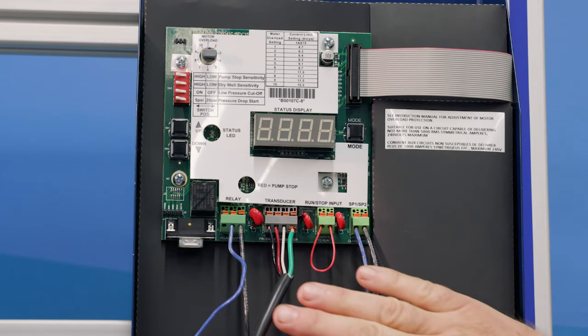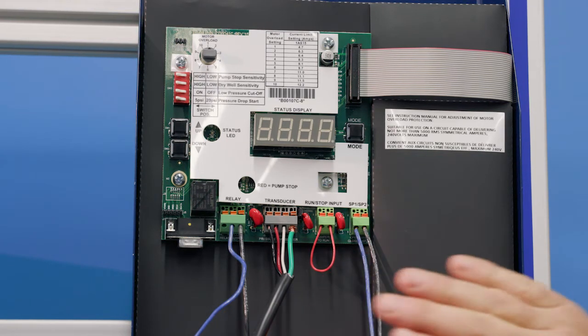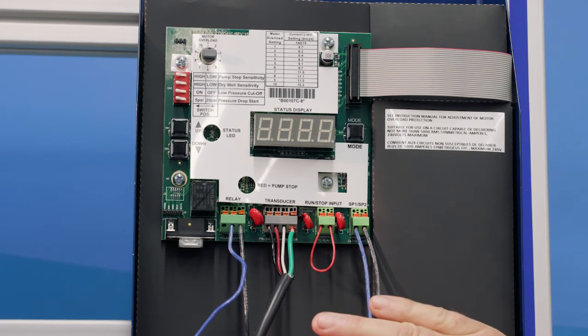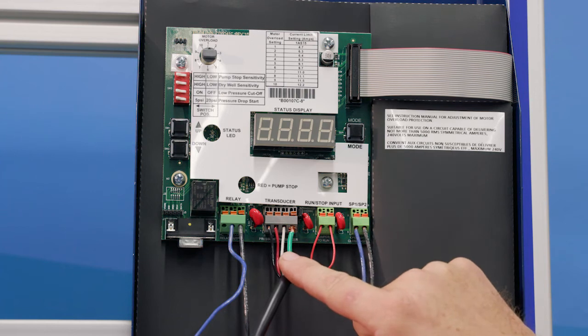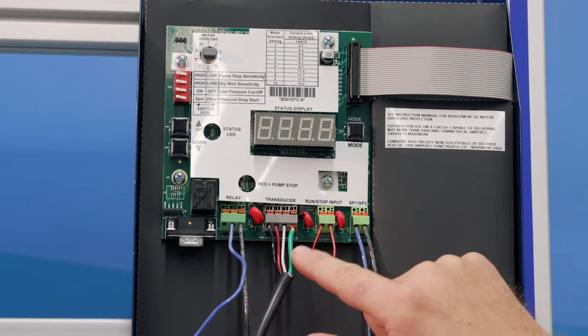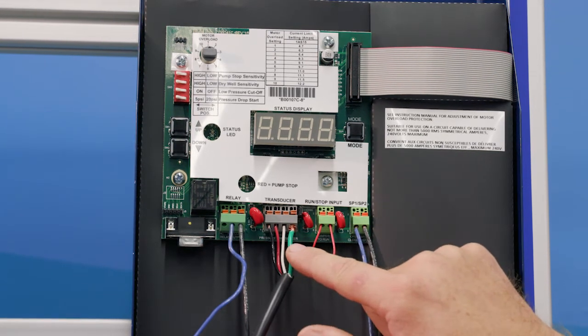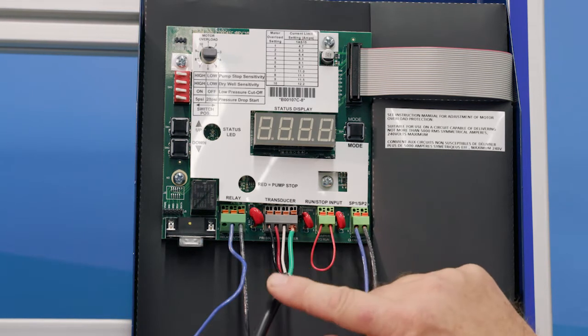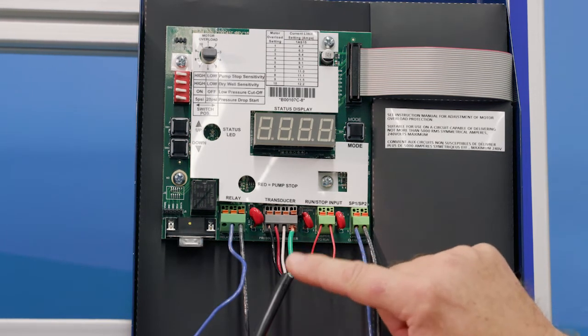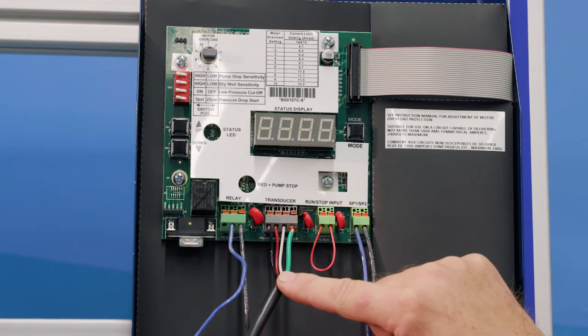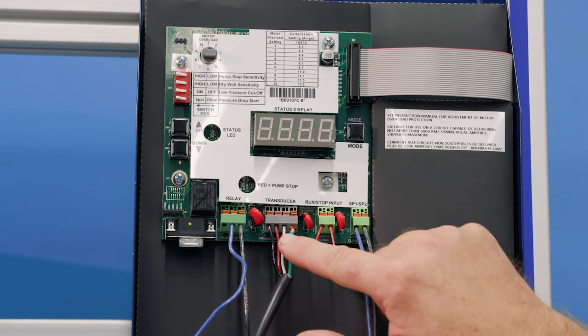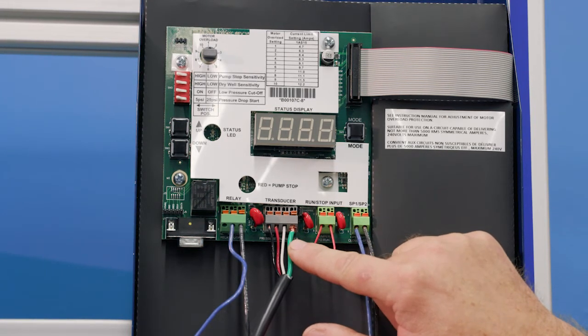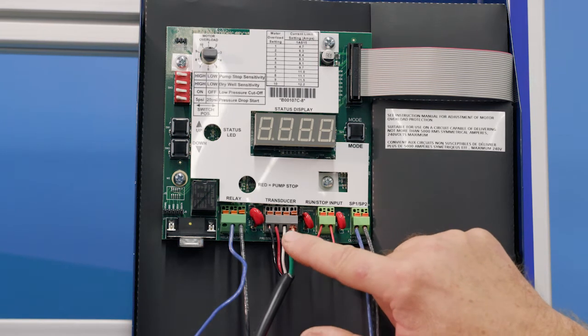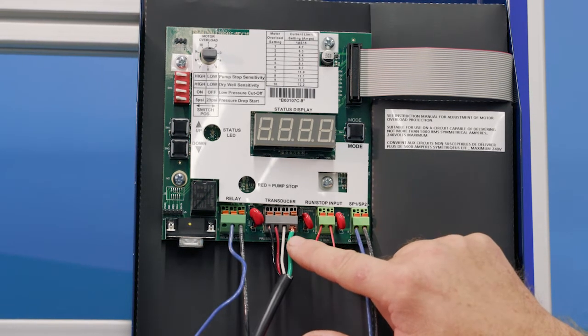Now, for now, we're just going to focus on the wiring out of the box for the drive. That would be your transducer, your sensor. That's all pre-wired, but it is color-coded, so in case we need to shorten this wire or put another cable in there, then we know how to wire that up because it's all color-coded. So black, red, white, green.